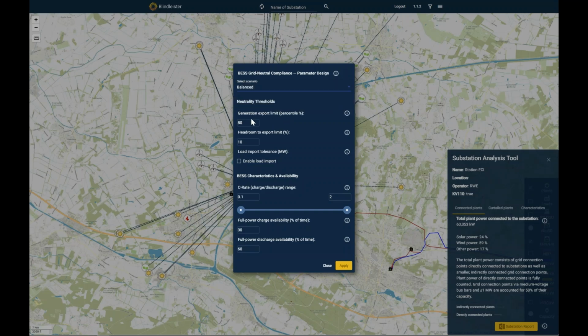So how can we do it? We can choose a certain scenario. If we are conservative, we take conservative. If we want a more balanced approach, we take balance. If we're optimistic, we take this. If we take balance, we consider the 80th percentile of the generation of the last 12 months, which we compute in 15-minute steps. We consider it for weekends, for weekdays, but also for different seasons. So it's dynamic. We can also define a certain safety margin below this, which is here 10%. And we can also tick to enable load import.